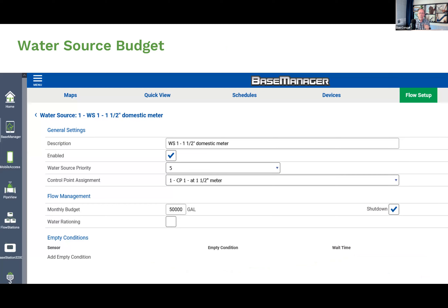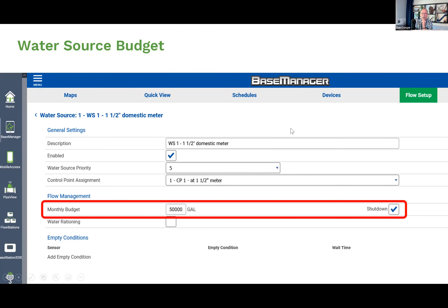The last feature is the water source budget. In Base Manager, under water sources, I've set a 50,000-gallon monthly budget for an inch-and-a-half domestic meter with the action set to 'shutdown.' When more than 50,000 gallons have been used through that meter in a 30-day period, two things happen: I receive an alert and that water source is discontinued. If there's a lower-priority water source available, it rolls right onto that one automatically.